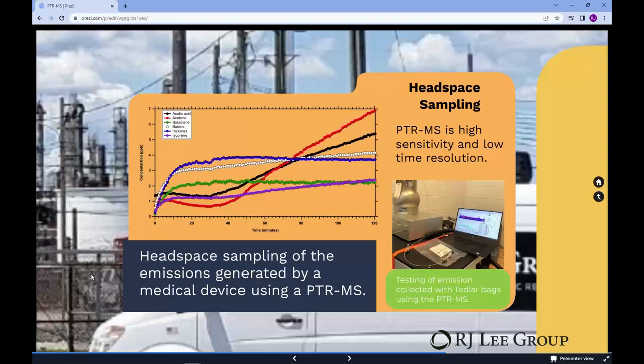In a previous study, RJ Lee Group investigated the compounds emitted by a medical device. The device was placed in a testing TEDLAR bag filled with clean air, and the PTRMS was used to monitor the VOC concentration inside the bag. After the device was turned on, the concentration of six compounds increased. After two hours of testing, compounds such as butadiene and hexenes had reached a plateau at a concentration lower than 5 ppb. The concentration of acetone, acetic acid, isoprene, and butene continued increasing during the whole testing period.